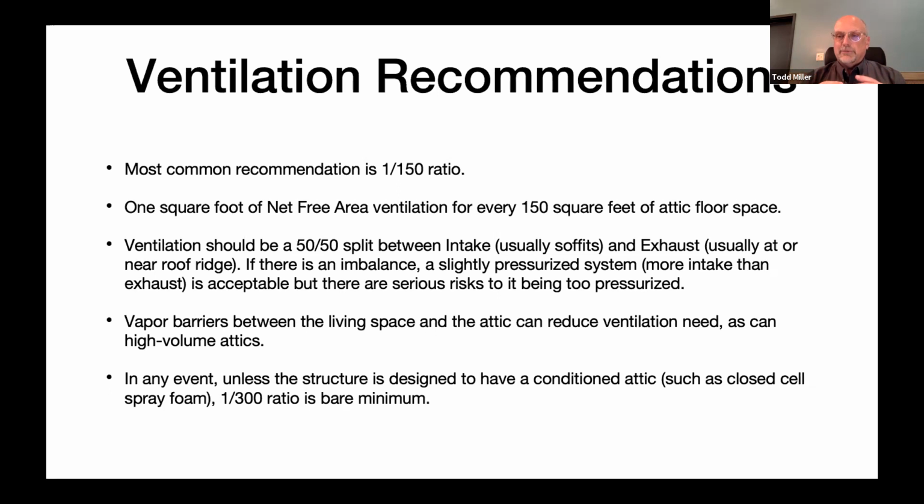because of the very, very tight airspace. That small home with the tight airspace in the attic, they got the same stuff going on inside of that house as the people with a 10,000 square foot home do in terms of cooking and bathing and laundry and things that create moisture, but they have a whole lot lower space for that moisture to be dispersed. And so a much greater likelihood of condensation occurring.